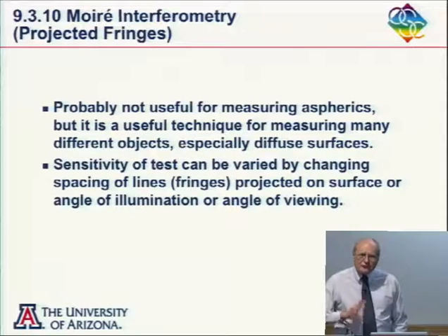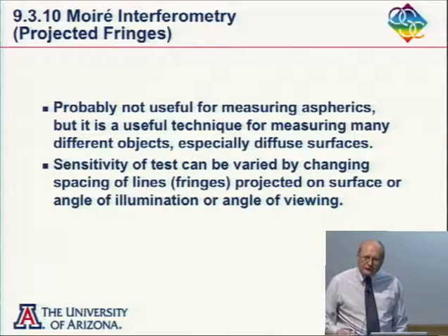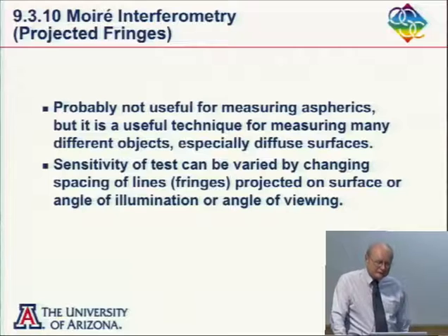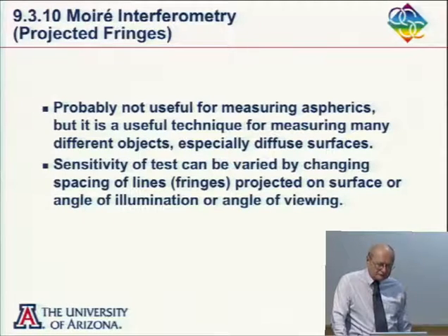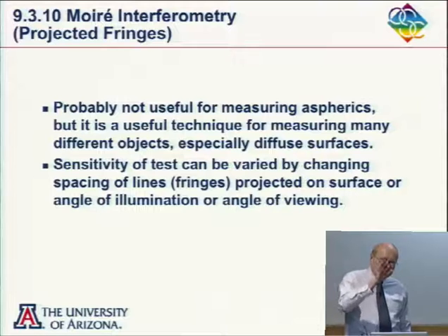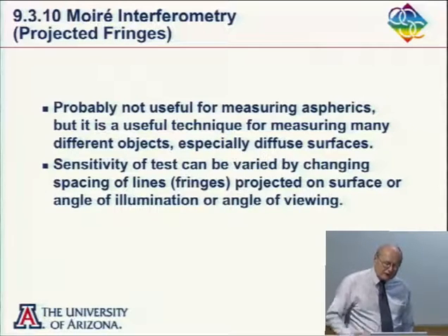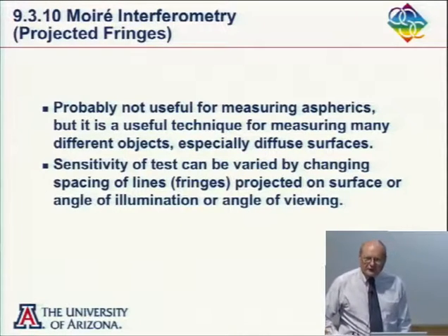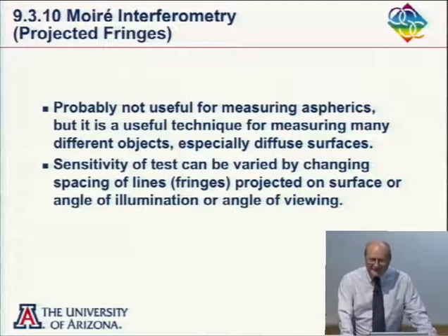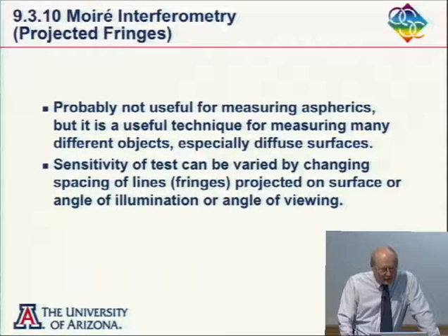We're not going to measure slope here. We're going to actually measure the shape. So that's one major difference from SCOTS. And we're also going to project the fringes onto the surface. And in SCOTS, you have it some distance away. So it's a cousin maybe, but not a brother or sister.